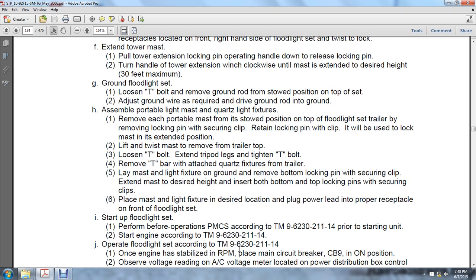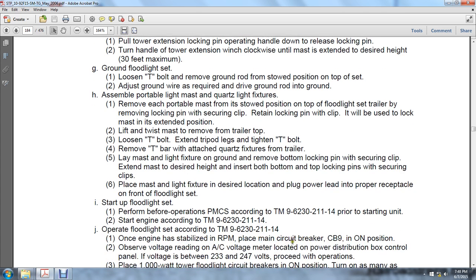Start up the floodlight set. Perform before-operation preventive maintenance checks and services, TM 9-6230-211-14. Prior to starting operation, start the engine according to TM 9-6230-211-14. Operate the floodlight sets according to TM 9-6230-211-14. Once the engine has stabilized RPMs, place the main circuit breaker, CB9, in the on position.